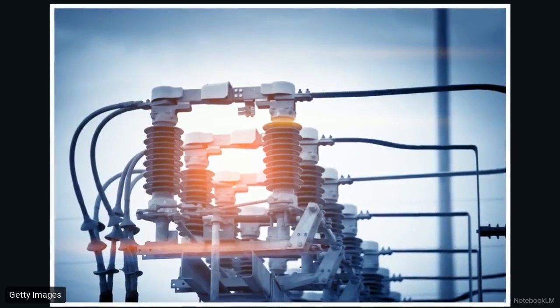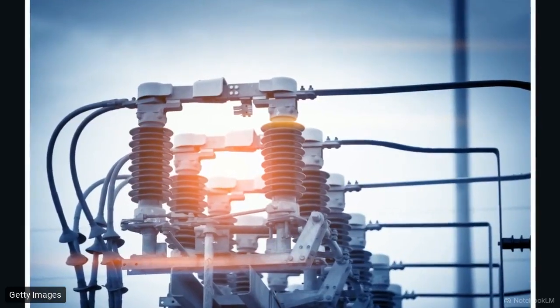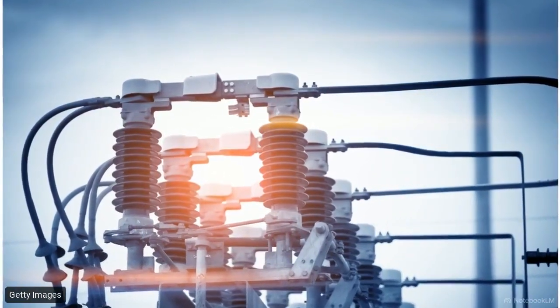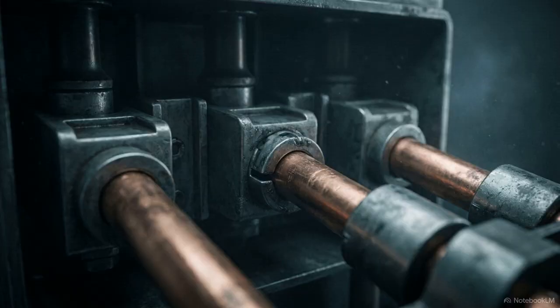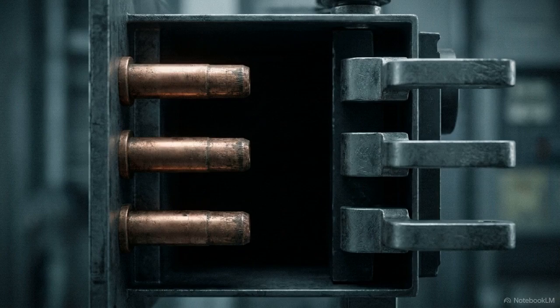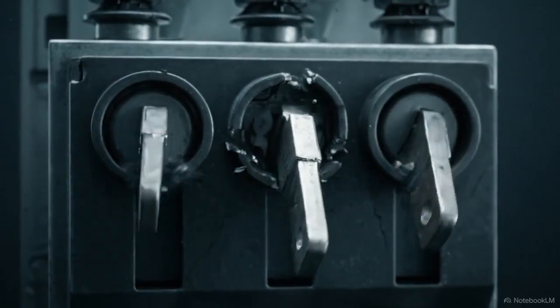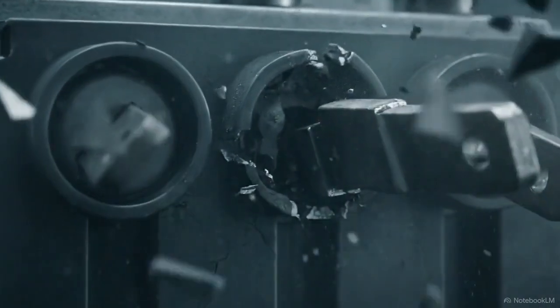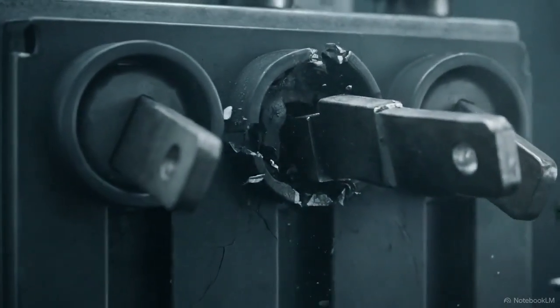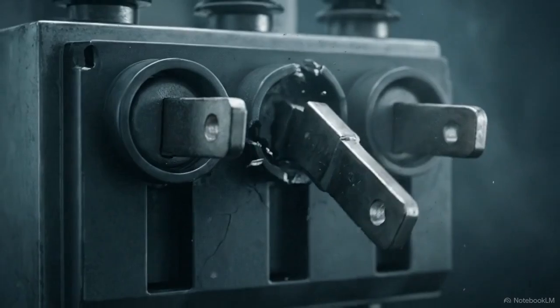The mechanical gatekeeper controlling the flow of electricity from the turbine to the grid is called a vacuum circuit breaker. To safely cut the power, this breaker is designed to snap open all three of its electrical phases simultaneously, creating a physical gap that current cannot cross. But occasionally, a microscopic mechanical failure occurs. The switch fires, two poles snap open, but the third pole jams, physically stuck in the closed position.